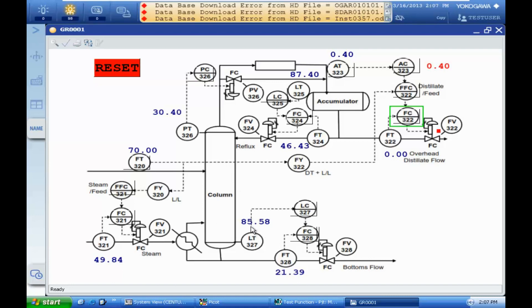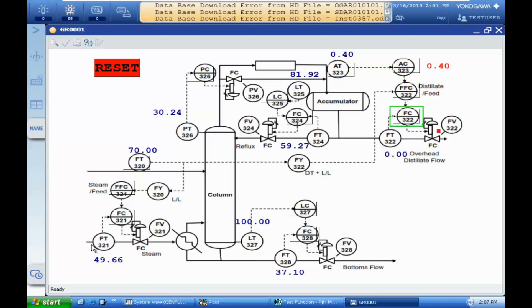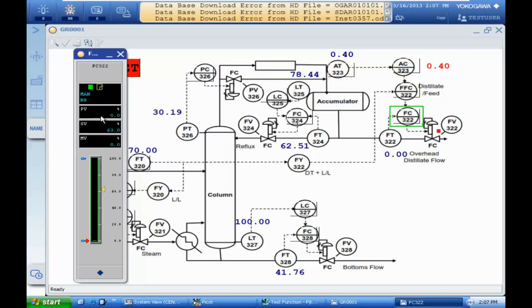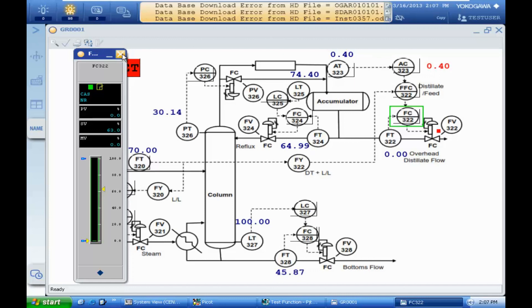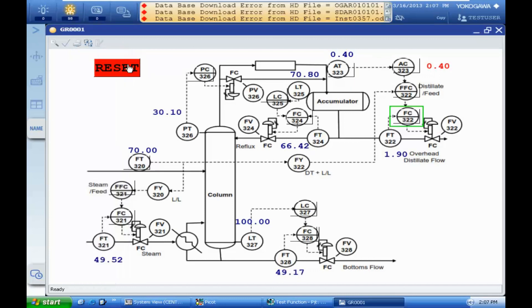The level is getting close to the max — it's a safety risk. In normal cases, we should have some shutdown valves here, and shutdown valves for steam, and the column should be isolated. But here we don't have those safety measures, so I changed the output control to cascade mode in order to maintain normal operation.